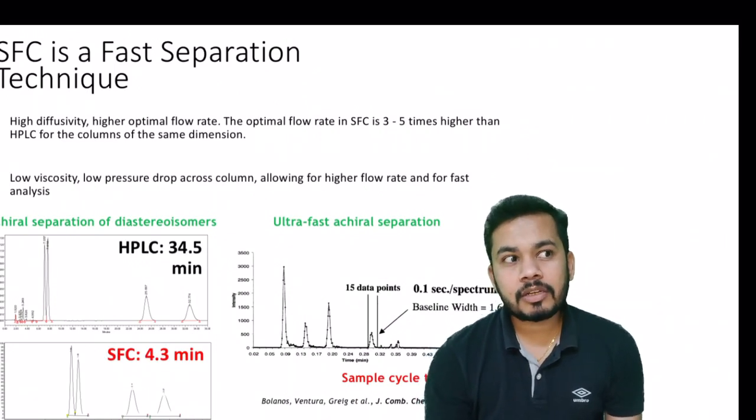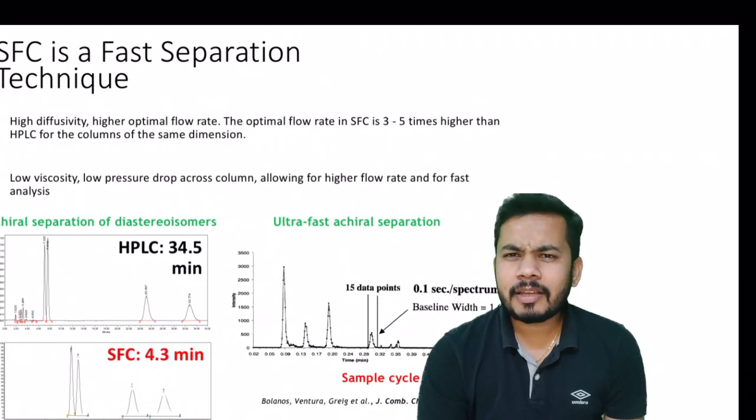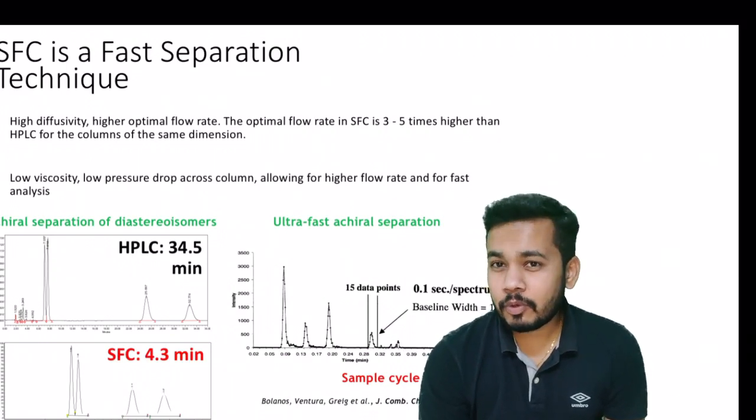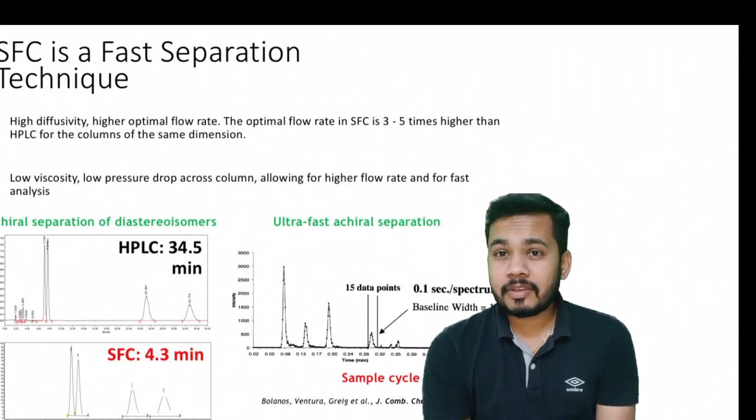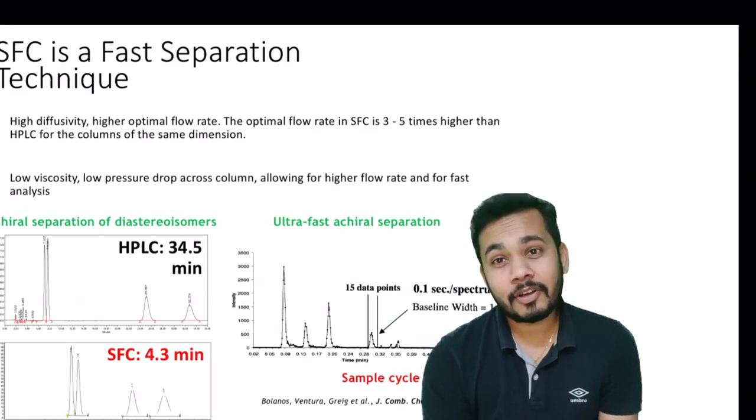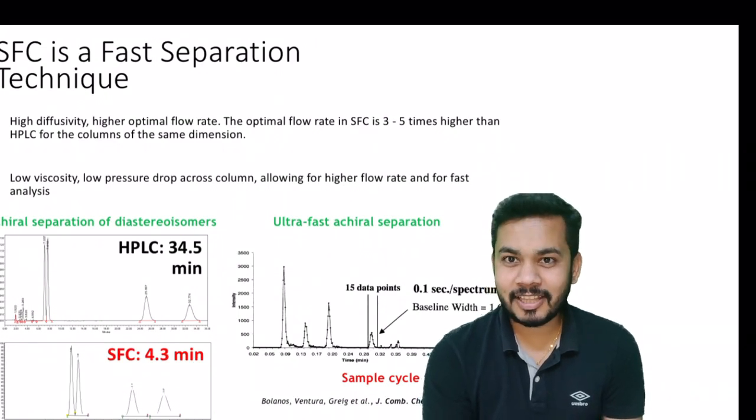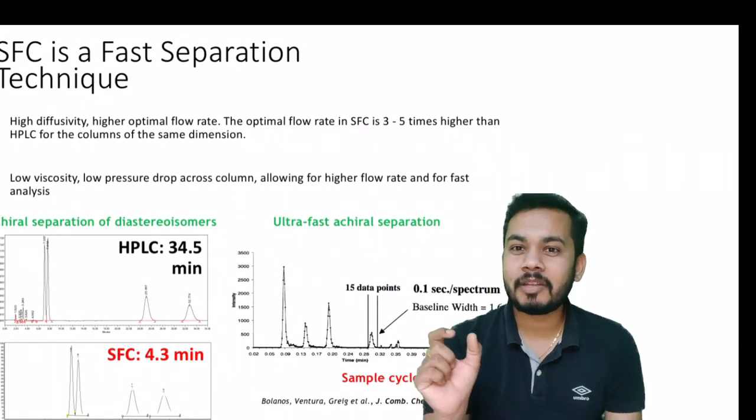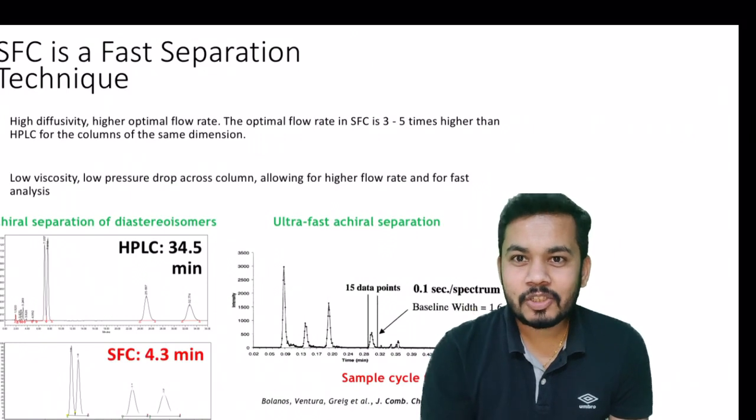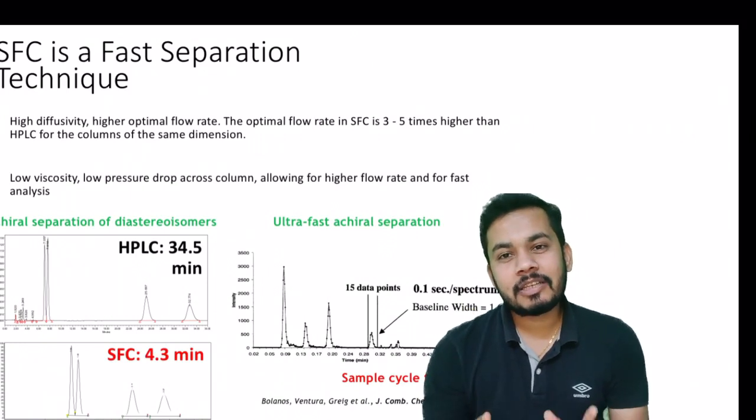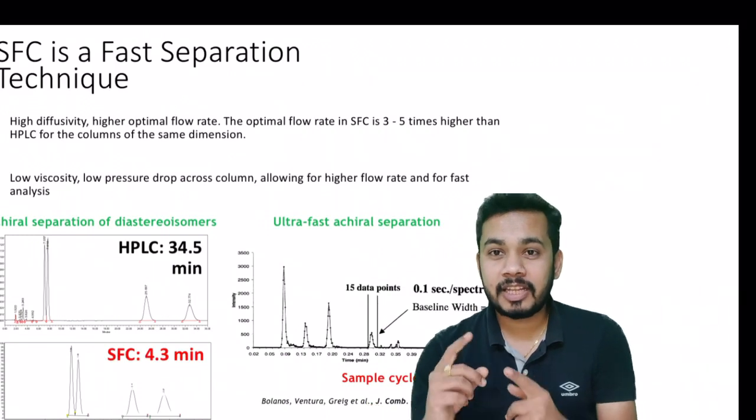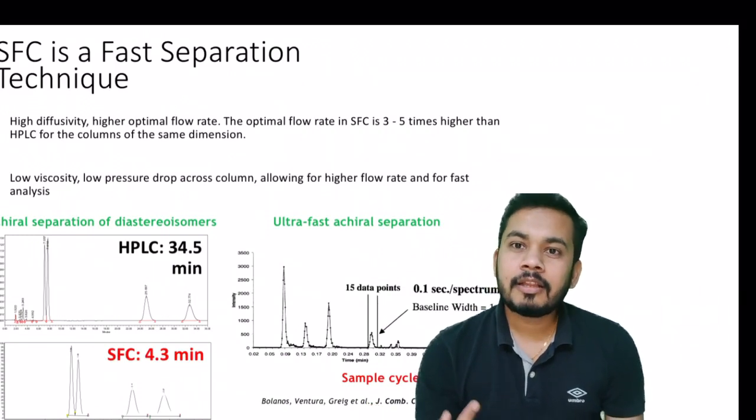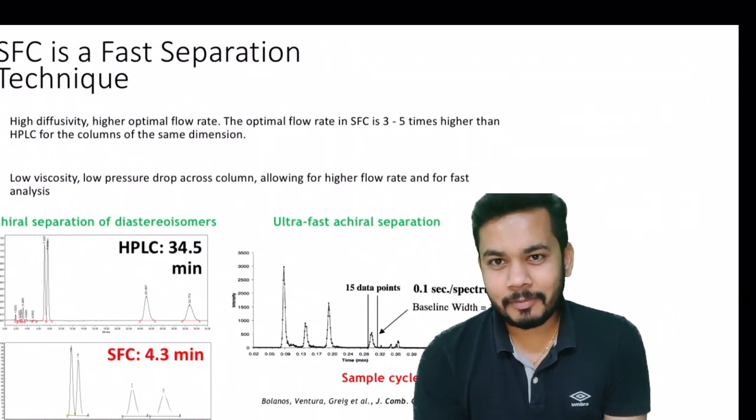If we talk about runtime and comparison, typically HPLC has a runtime of 40 to 50 minutes. UPLC can reduce runtime up to 5 minutes. But for SFC, the remarkable thing is that runtime can be minimized to 1 minute. So HPLC which takes 40 to 50 minutes for a single run analysis, SFC will take only 1 minute.